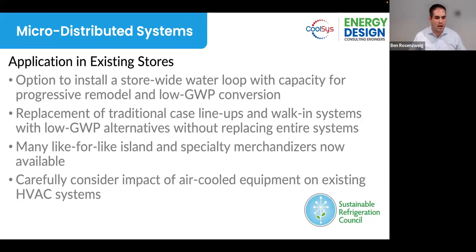So this is my last slide, and then I'll wrap up. Application in existing stores. So you have the option to install a store-wide water loop with capacity for progressive remodels and low GWP conversion at existing stores, replacement of traditional case lineups and walk-in systems with low GWP alternatives, one by one, whole store, department by department, depending on how you want to do it. There are now many commercially available like-for-like island and specialty merchandiser cases. And you should carefully consider the impact of air-cooled equipment on existing store HVAC systems. So really, when you implement this type of system into an existing store, it's important to work with your designers and your engineers to make sure you're getting a system that won't sacrifice the environment in the store from an HVAC perspective, but can help you achieve your low GWP goals as a company on a store-by-store basis and across the country.